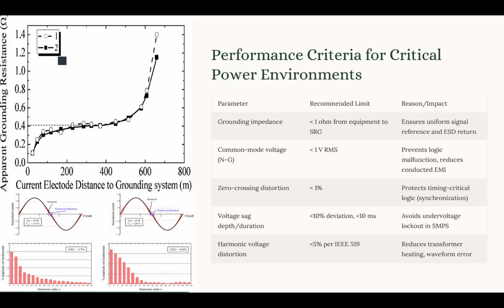Now, we also have the harmonic voltage distortion criterion, which has been mentioned. It is based on IEEE 519, and it should be less than 5% THD. This is voltage distortion. IEEE 519 has limitations for current distortion and voltage distortion, and please make sure that you distinguish that this 5% is for THD. On that IEEE 519, we have two parameters that quantify the distortion. One is THD, which is total harmonic distortion. Another one is TDD, which is the total demand distortion. This 5% is for THD on a voltage. Okay, so it is important to make sure that we consider all those specific definitions.